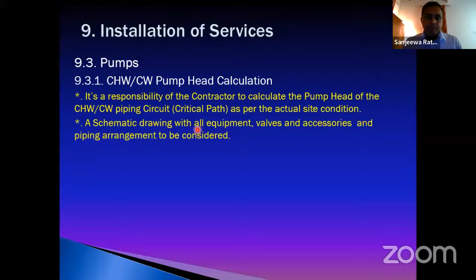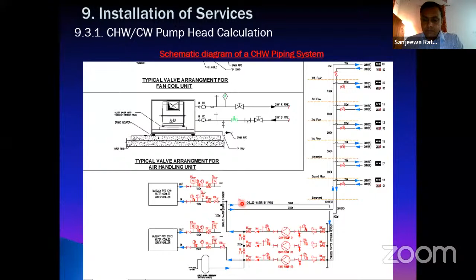For example, here in one of the projects, I just want to show the schematic diagram of the pumps. These two are chillers, and this is the common header with the connection to all the chilled water pumps and all interconnected. And this is a 7-story building, and the pipe network is elaborated here. So the critical path is obviously this topmost path, and again he has to consider the terminal equipment, an AHU or maybe a fan coil unit, at the longest path. All the bends, all these valves and pump headers, and everything, including the chiller evaporator coil pressure drops, must be considered when sizing the pump.